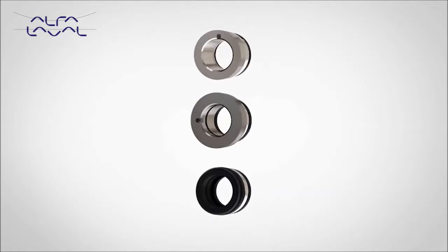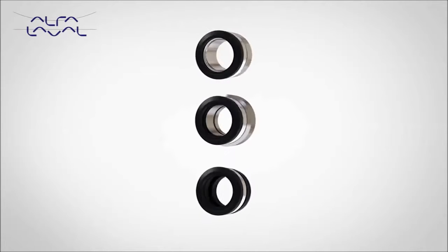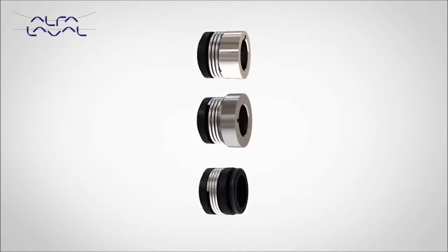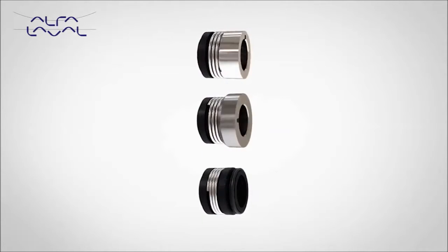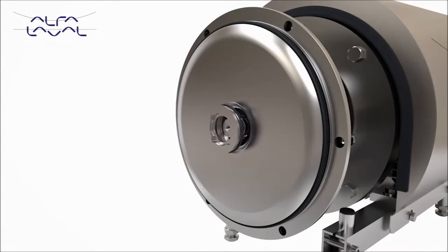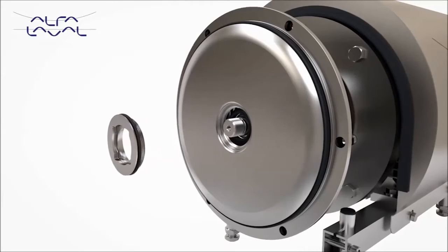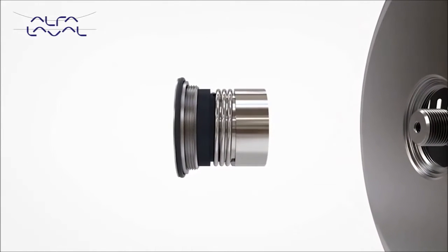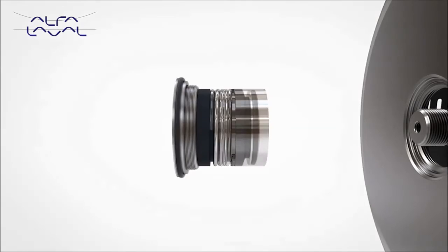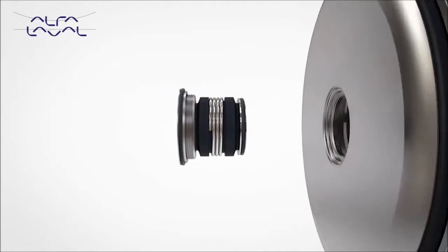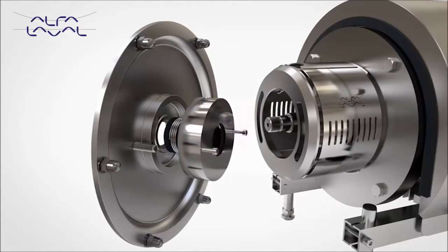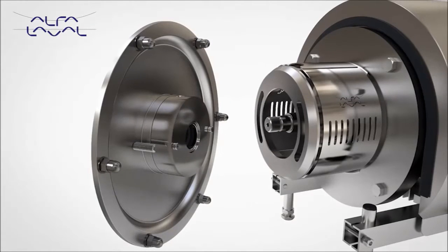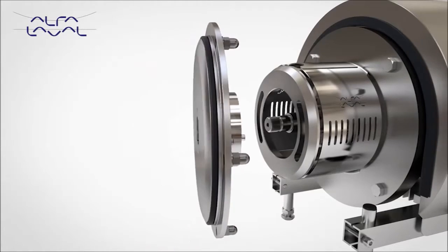The LKH pump is available with three seal options: single, single flush, and double mechanical, each option having a range of seal faces and elastomers to meet user application needs. The universal design also allows for easy retrofit conversion from single to single flush or double seal without component modification, enabling the user full process flexibility to change sealing solution should pump application change.